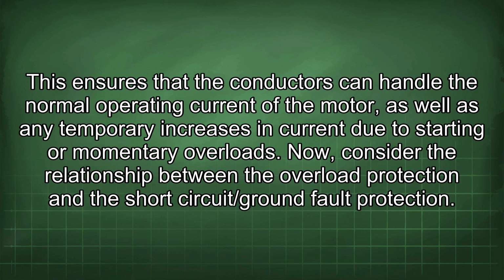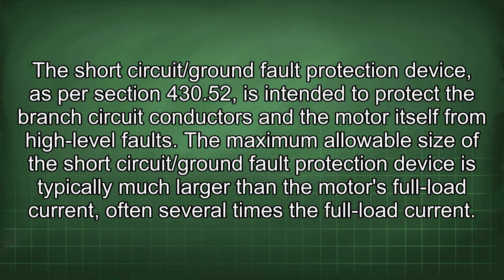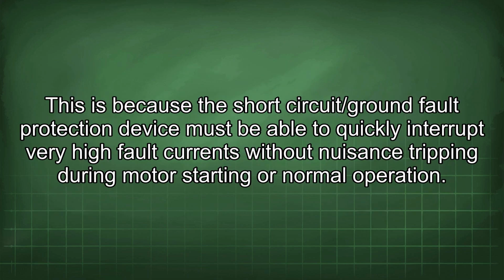Now, consider the relationship between the overload protection and the short circuit/ground fault protection. The short circuit/ground fault protection device, as per Section 430.52, is intended to protect the branch circuit conductors and the motor itself from high-level faults. The maximum allowable size of the short circuit/ground fault protection device is typically much larger than the motor's full load current, often several times the full load current. This is because the short circuit/ground fault protection device must be able to quickly interrupt very high fault currents without nuisance tripping during motor starting or normal operation.